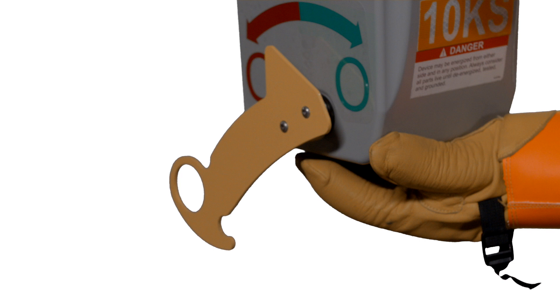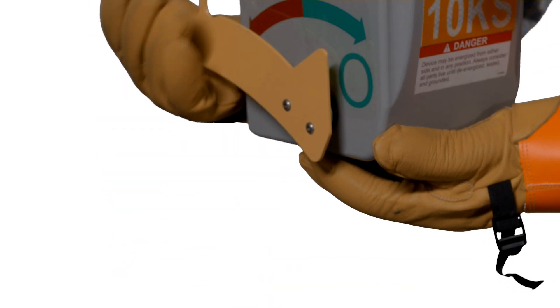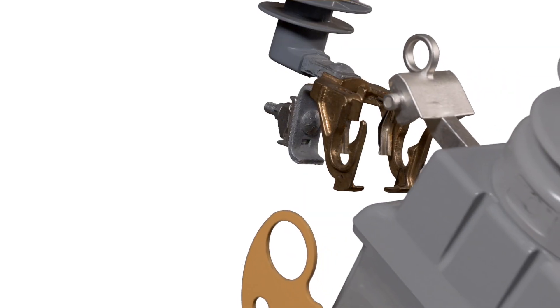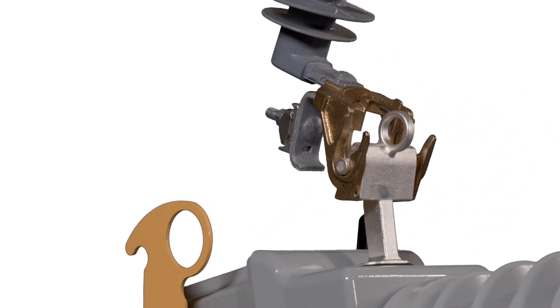Make sure the open-close lever is in the open position. The interrupter can be easily opened by pushing up on the curved indent in the lever. Insert the VacuFuse Interrupter into the cut-out mounting by carefully guiding the trunnion of the interrupter into the hinge end of the mounting.